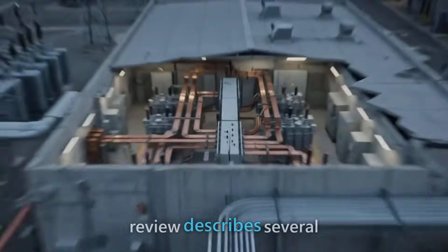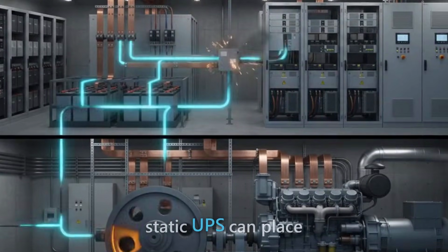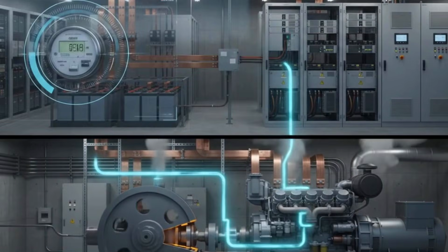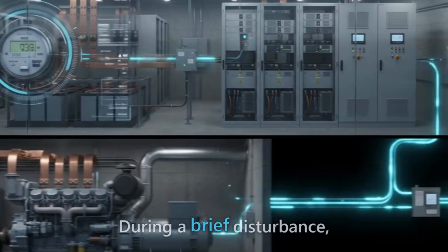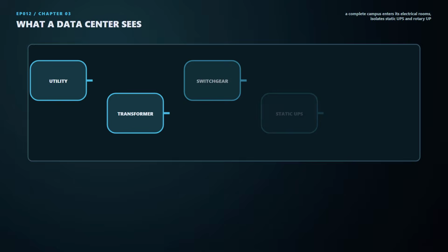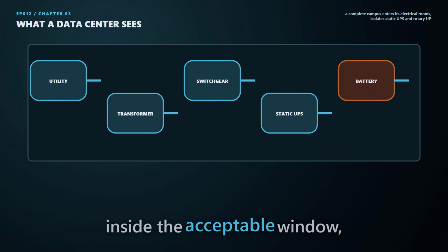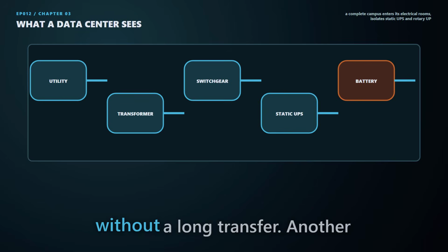NERC's incident review describes several broad arrangements. A static UPS can place a battery and power electronics between the grid and the load. During a brief disturbance, the battery supports the servers. If grid voltage returns inside the acceptable window, the system can settle back without a long transfer.